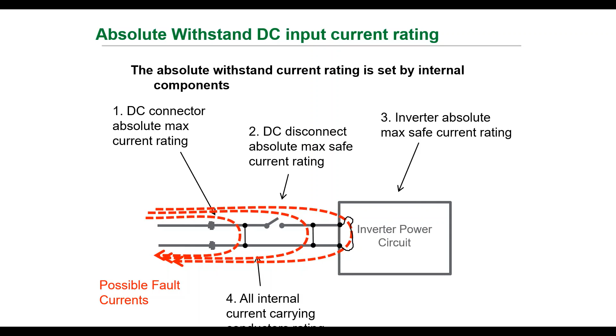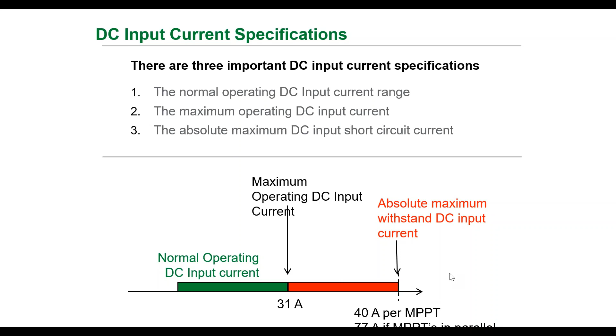So here 31 ampere is the nominal operating current, normal operating. That is maximum current, Imax. Imax is 31 ampere, and ISC, short circuit current, is 40 ampere. So your design should be for 40 ampere, not for 31 ampere. So this is the solar system.